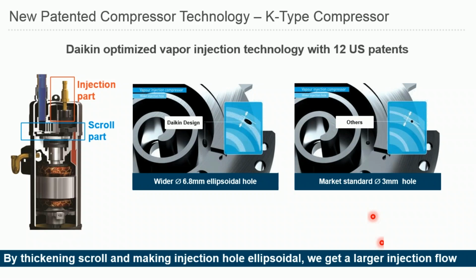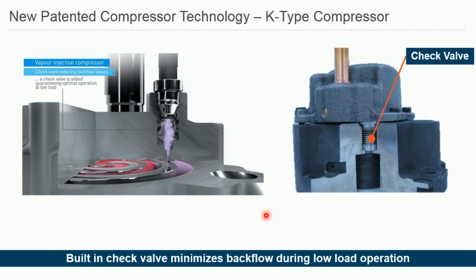There are a couple of things that make our compressor design different from others. One of the main things is this special, unique vapor injection hole design. Instead of using a smaller hole like you see over here, a 3mm hole that you see in most compressor designs available with other manufacturers' products, we're using an ellipsoidal hole. It's much larger compared to this 3mm hole. It gives you more vapor injection, allowing you to achieve higher capacities in low ambient temperature situations. It also helps from a reliability standpoint with the addition of this check valve, especially at low load operations. Using that bigger injection hole, your compressor will be running at a more reliable operation level.